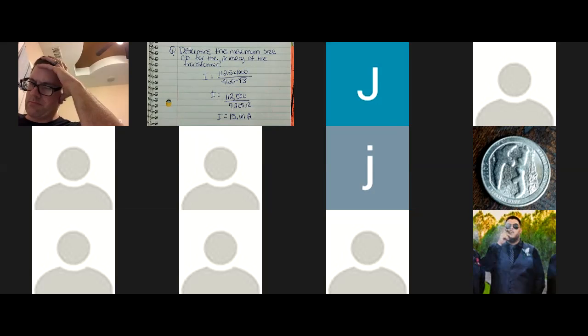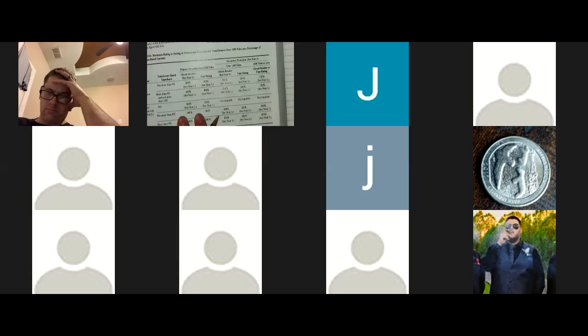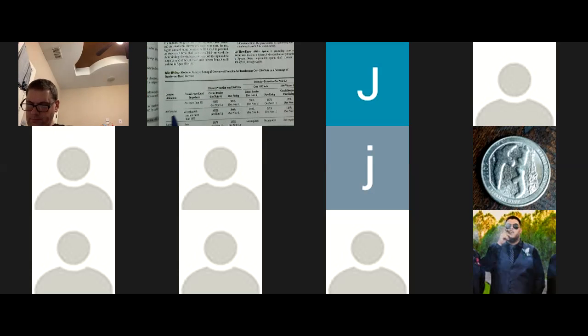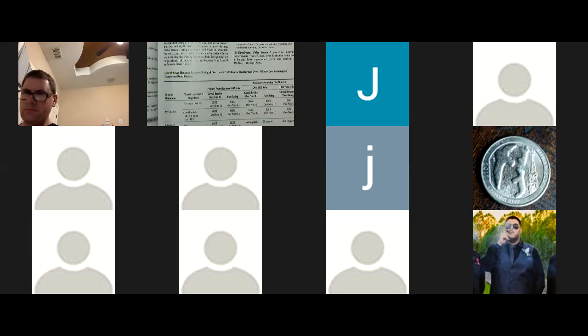So okay, now we have that. Once again, I go to my chart, 450.3(A). My impedance is 4%. It's non-supervised, so I'm going to put any location. Is it not more than 6 or more than 6? Well, it's not more than 6. I'm focusing on my primary, and it's going to be an enclosed circuit breaker, so it's going to be 600%. And of course, if you read note 1, where the required fuse rating or circuit breaker setting does not correspond to a standard setting, a higher rating that does not exceed the following shall be permitted. And then it gives you those 2 rules right there too.